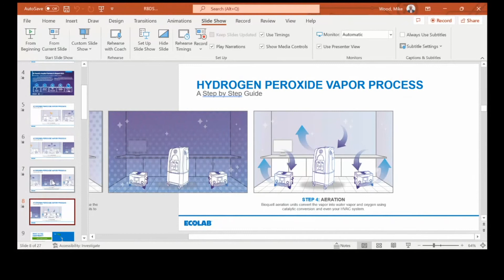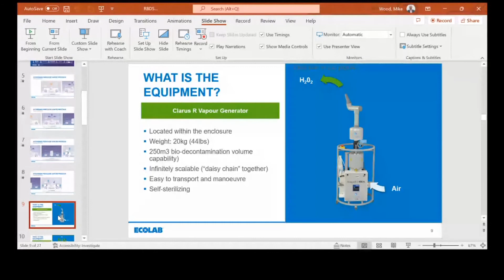So what is the equipment? This is a Clarus R vapor generator, located within the enclosure. It weighs 20 kgs and is built so that 2 engineers can carry either side, holding a handrail while walking up a flight of stairs. They're built to do 250 meters cubed, with a volume of 50 meters cubed each. We can infinitely daisy chain these together, hooking as many systems as we want, all speaking back to a central control panel outside the target envelope. They're easy to transport and maneuver, and they're self-sterilizing.